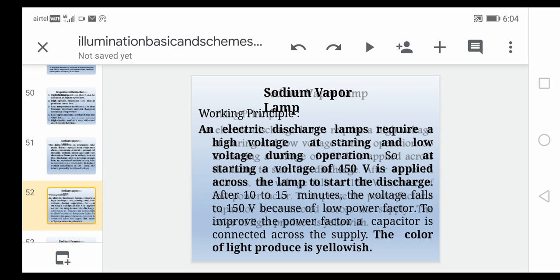An electric discharge lamp requires a high voltage at starting and low voltage during the operation. So at starting, a voltage of 450 volts is applied across the lamp to start the discharge. After 10 to 15 minutes, the voltage falls to 150 volts. Because of low power factor, to improve the power factor, a capacitor is connected across the supply. The color of light produced is yellowish.